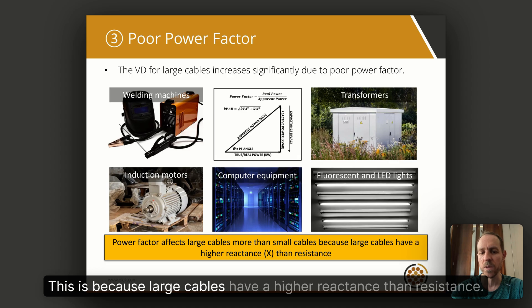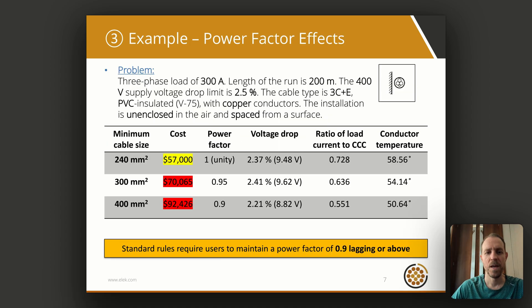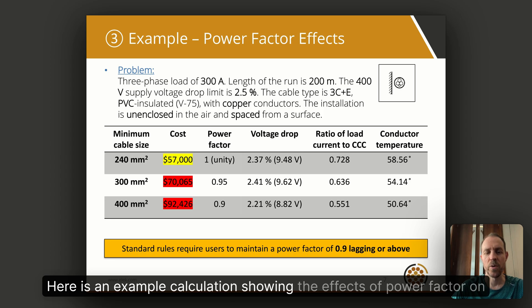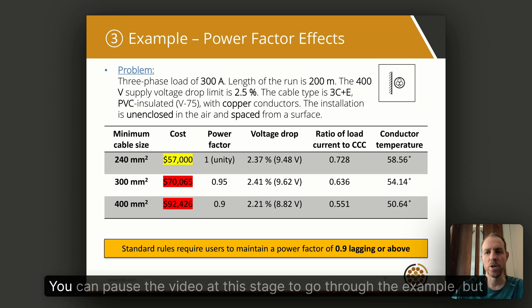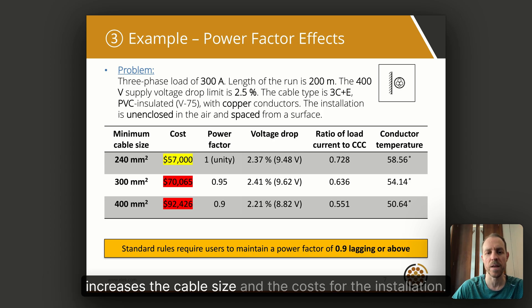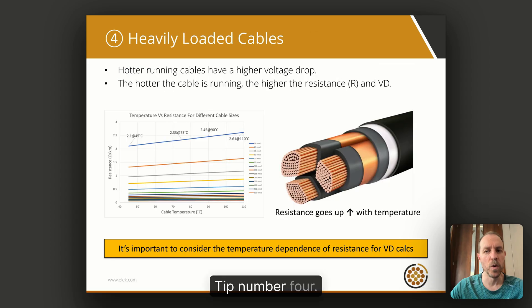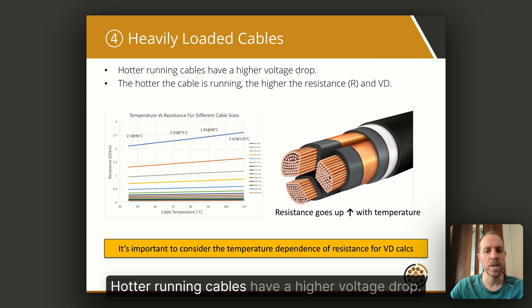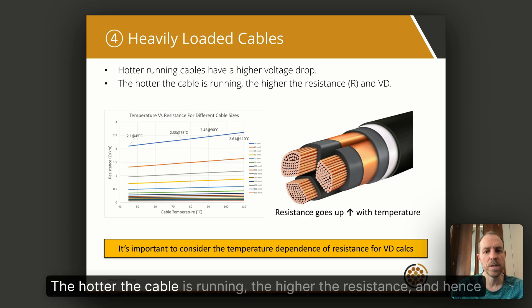This is because large cables have a higher reactance than resistance. Here is an example calculation showing the effects of power factor on voltage drop. You can pause the video at this stage to go through the example. Ultimately, you'll see that a small change in power factor significantly increases the cable size and the costs for the installation.